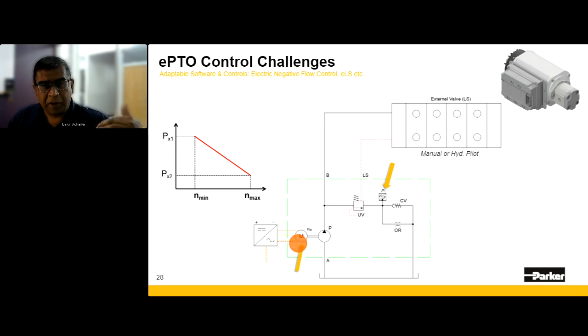And when the pressure starts dropping, because the functions are demanding all the flow, your PX value is going to start dropping, and then all you do is speed up the motor. So it's a very simple controls concept you can use.